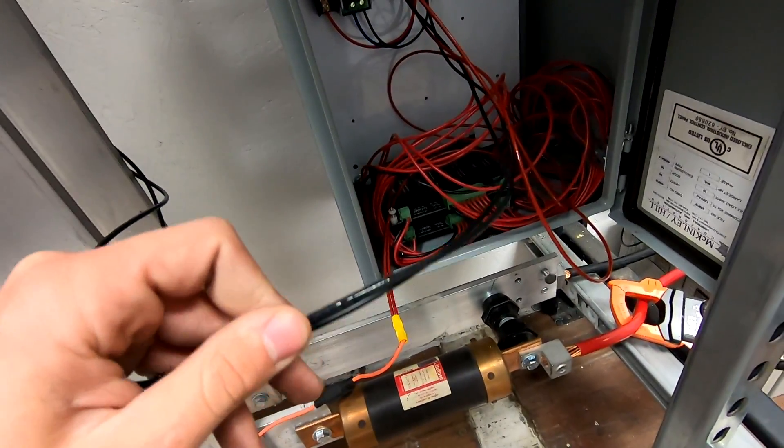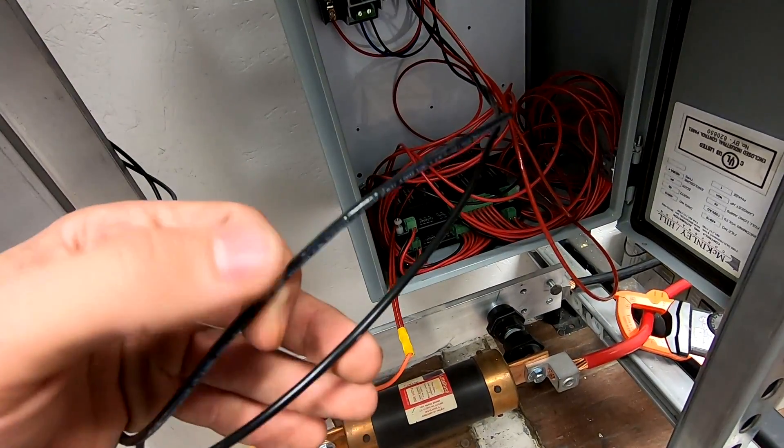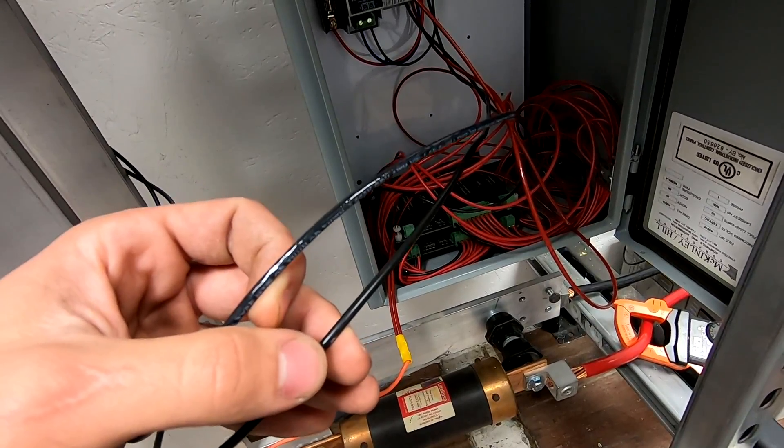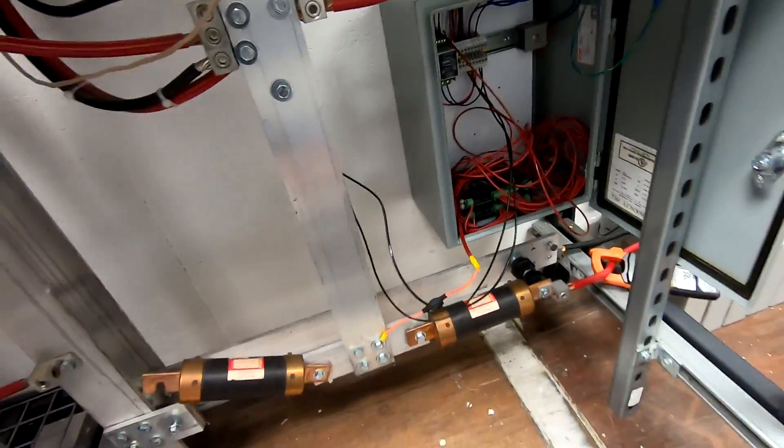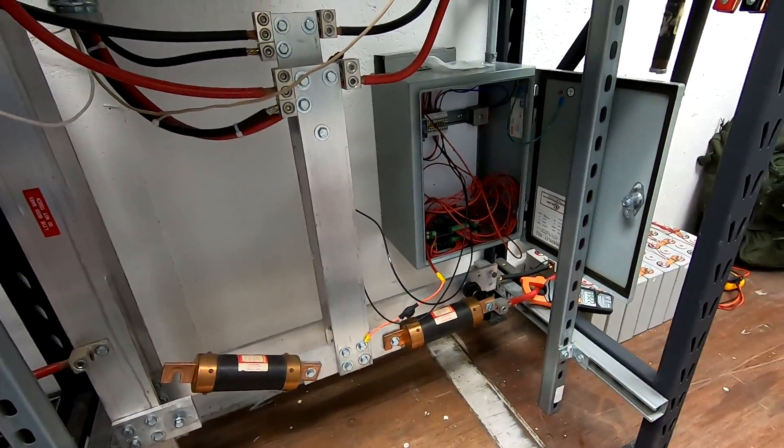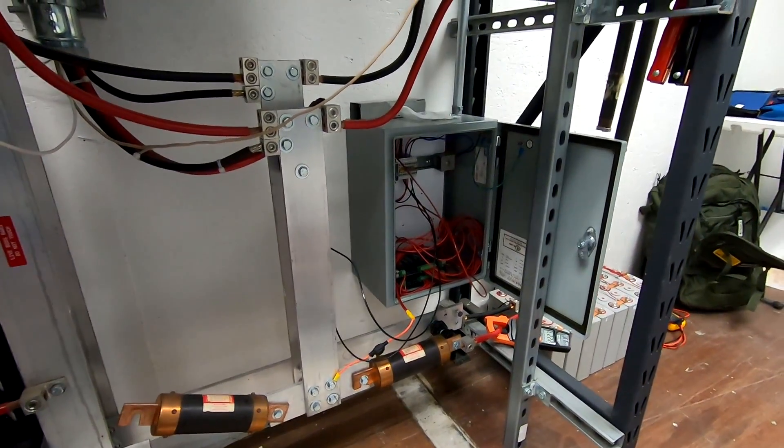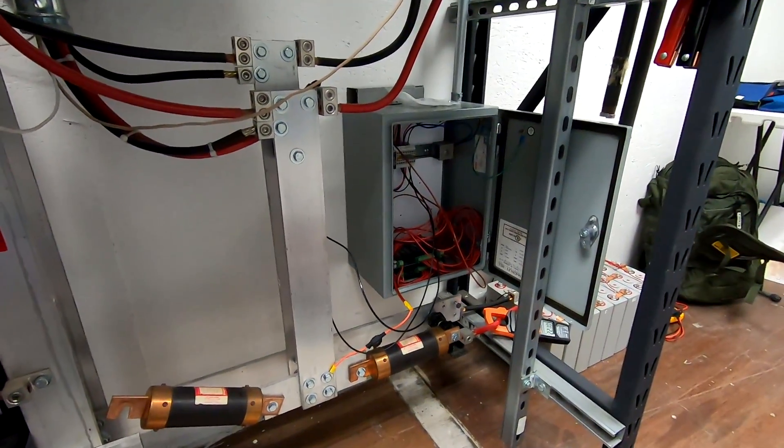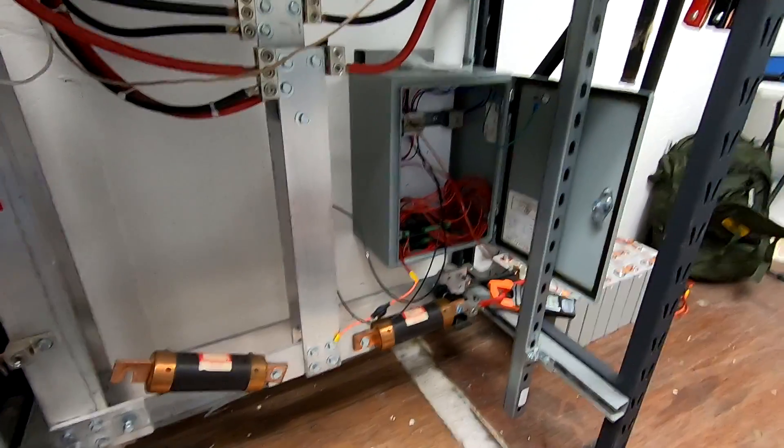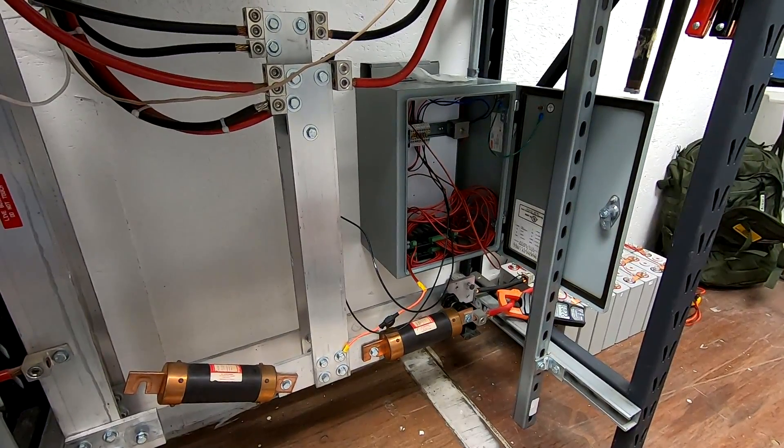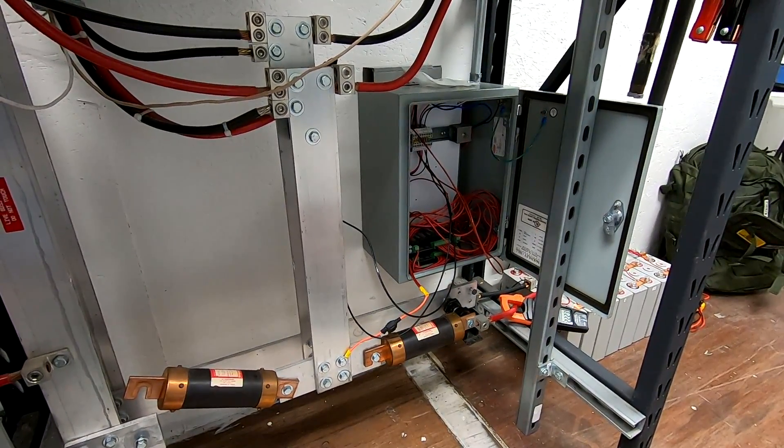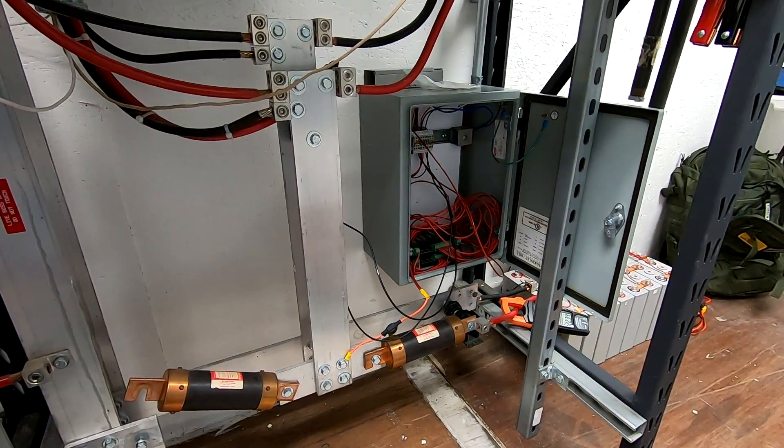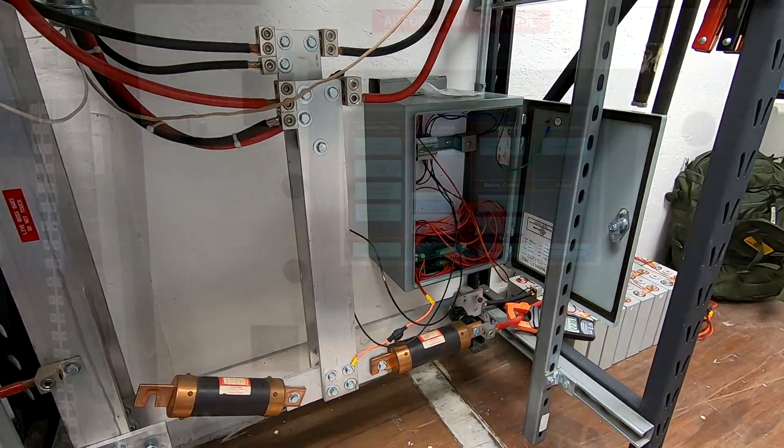And the reason I have two of these, there's a number 12 wire, which is this one, and a number 16 wire, which is this one. The number 12 wire is the current carrying wire that feeds power to the DC to DC converter for the PLC. And the number 16 wire is the voltage sensing line for the transducer to make sure we get accurate readings at the bus.